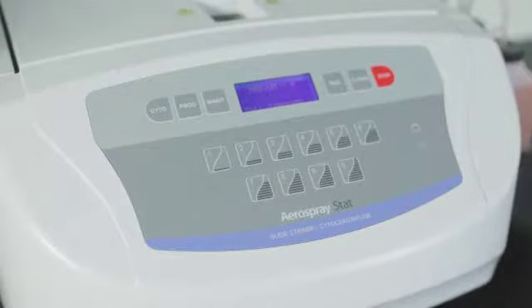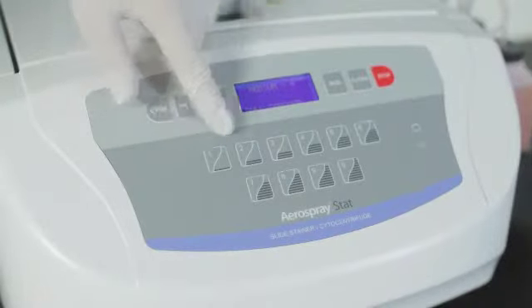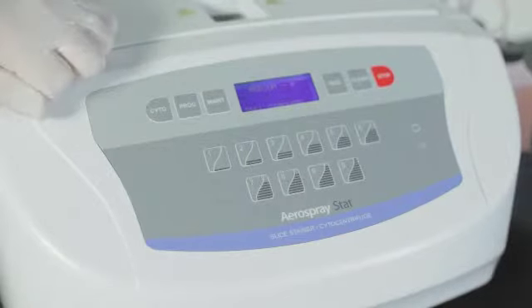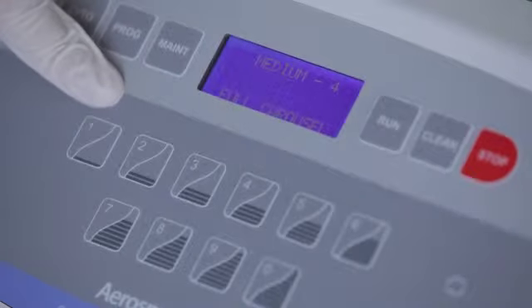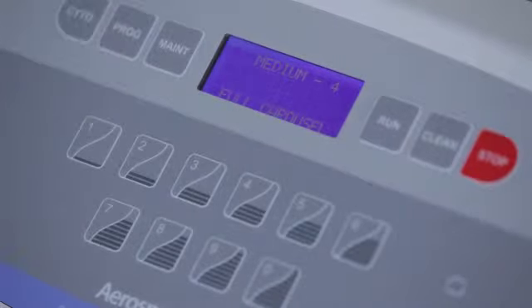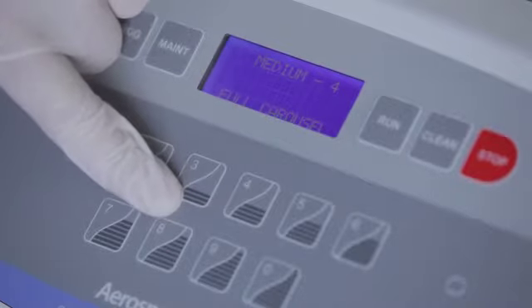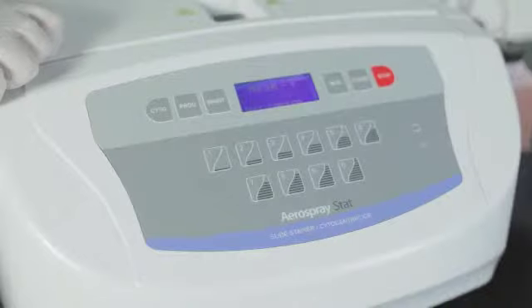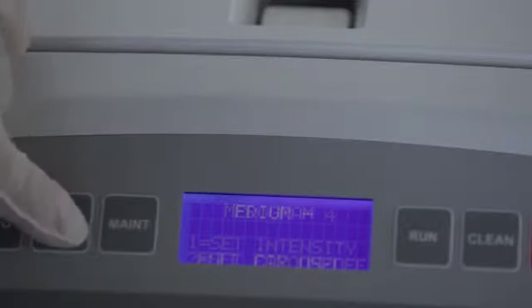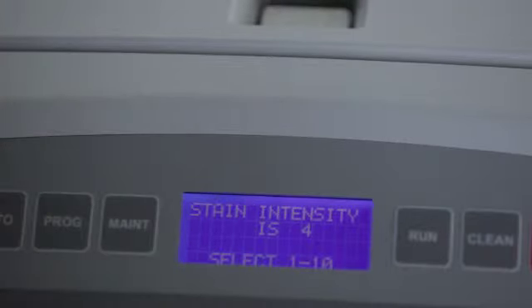The firmware for the Hematology Stat Stainer includes 10 preset intensities. Intensities 1 to 10 stain blood smears and bone marrow samples lighter to darker. Generally, the lower intensities stain the slides lighter and more red than the higher intensities. Intensities 8 to 10 are primarily reserved for bone marrows. The factory default setting is the medium 4 setting. To change the intensity, press the prog button, then select the desired intensity.